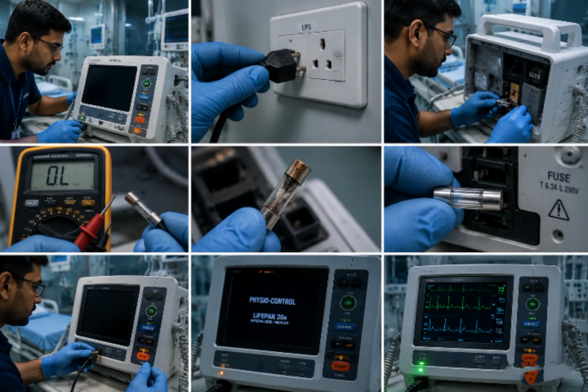Now open the rear fuse compartment carefully. You can see each and every step in the image. Now use a multimeter to test the fuse continuity. If the fuse is blown, replace it with the correct rating fuse. Reconnect the power cable, switch on the machine. The defibrillator now starts working successfully.